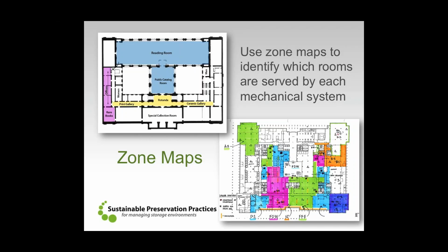Now these zone maps, you can do these in a number of different ways, and a number of institutions that I've worked with have already had these prepared. Others, and if you're one of the ones that hasn't worked on this or hasn't identified this yet, it's a good place to start. You pull out a set of mechanical drawings and you find the room or the space where the actual air handler might be, and you just begin tracing ductwork. You look at the supply air and look to see, all right, well, where does that go out into the building and what rooms does it serve?